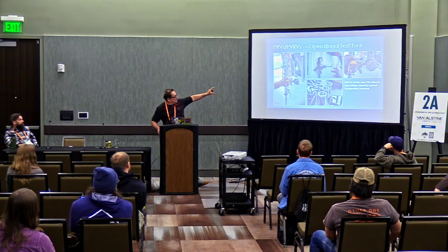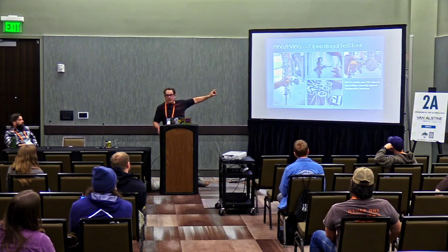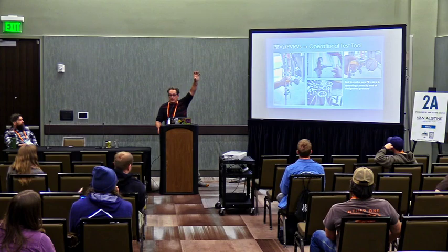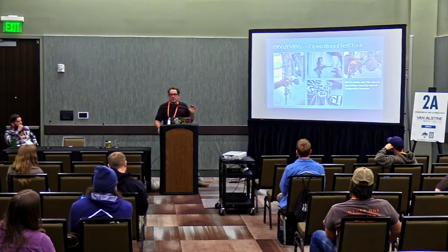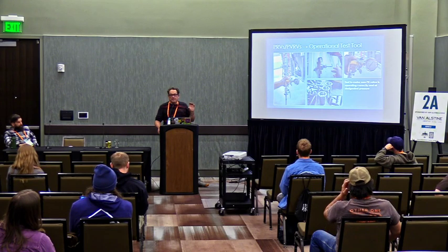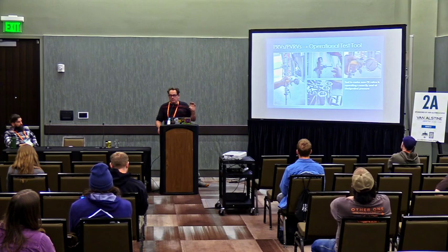This is a little difficult to see, but this is an apparatus for taking the pressure relief or pressure-vacuum relief off your vessel and putting it on this little apparatus that has a gauge on it, testing to see at what pressure that relief valve relieves.